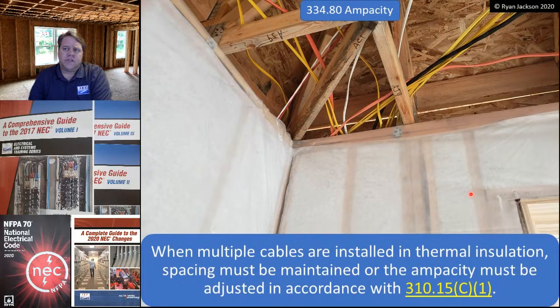Where multiple cables are installed in thermal insulation, spacing must be maintained or the ampacity has to be adjusted in accordance with the ampacity adjustment requirements. Well, yeah, but that's true whether we're in thermal insulation or not. Anytime I install multiple cables without maintaining spacing, you have to apply an ampacity adjustment. I hate that word bundled because the code doesn't use it, but you can't run a bundle of cables longer than 2 feet, right? Or you have to apply ampacity adjustment, whether that's in thermal insulation or otherwise.